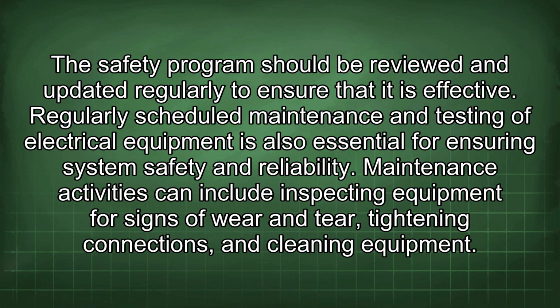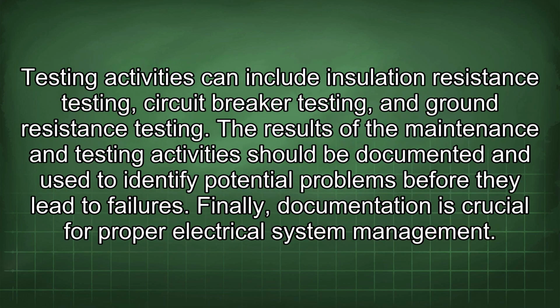Regularly scheduled maintenance and testing of electrical equipment is also essential for ensuring system safety and reliability. Maintenance activities can include inspecting equipment for signs of wear and tear, tightening connections, and cleaning equipment. Testing activities can include insulation resistance testing, circuit breaker testing, and ground resistance testing. The results of the maintenance and testing activities should be documented and used to identify potential problems before they lead to failures. Finally, documentation is crucial for proper electrical system management.